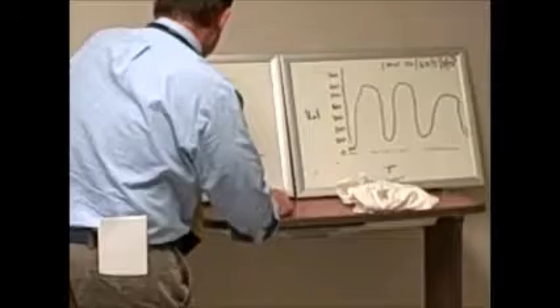But what does our pressure curve do? Machine breath, his breath, what's it going to do? He's going to trigger the demand valve, so it's going to go down, and then it can't go above what? 25. 30. PEEP of 5 and 25 of pressure support. So it can't go above 30. Okay? So if you have enough pressure support set for him, the only work of breathing he's doing is triggering the demand valve. Okay?